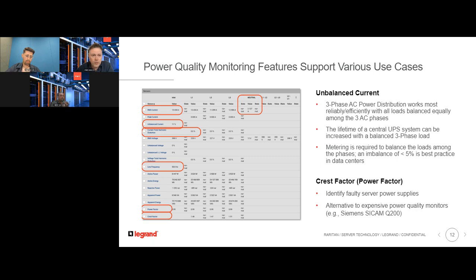We have also implemented another more advanced indicator for the same use case, which is called the current total harmonic distortion parameter, which is available as well. Usually very expensive measurement tools, like tools from Siemens, are able to measure crest factors or THDs only on individual load levels. And with our new PDUs, you're getting these very useful power quality indicators more or less for free.